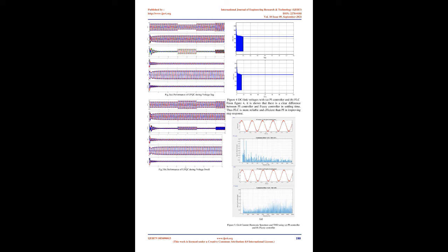The load reference voltage D-axis component equals the peak load reference voltage, since the PCC voltage and the load reference voltage have to be in phase with each other. The component of the Q-axis is kept zero. The series compensator reference voltage is obtained from the difference of the load reference and PCC voltage. Then the actual series compensator voltage is obtained by subtraction between the load and the PCC voltage.